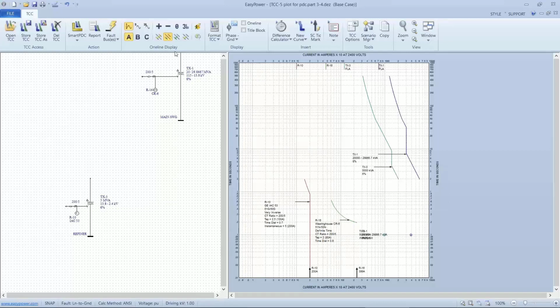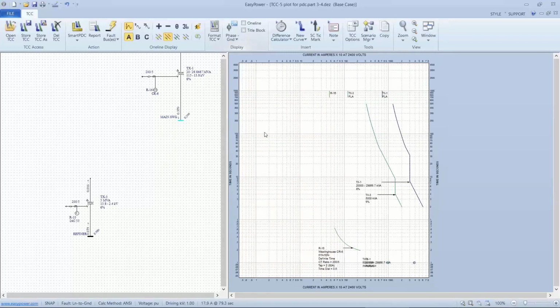So the takeaway is make sure you're doing a single line to ground fault, and you're looking at the ground current, because if you look at both, it doesn't really make sense. Just because the phase current will have a much higher result.